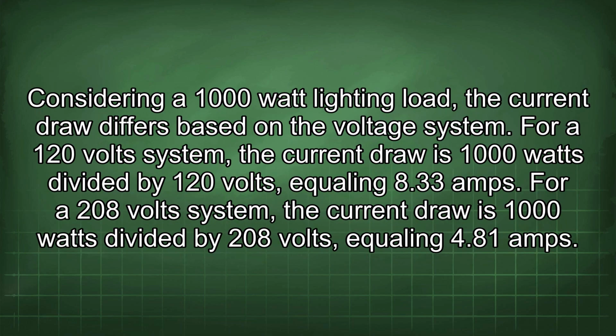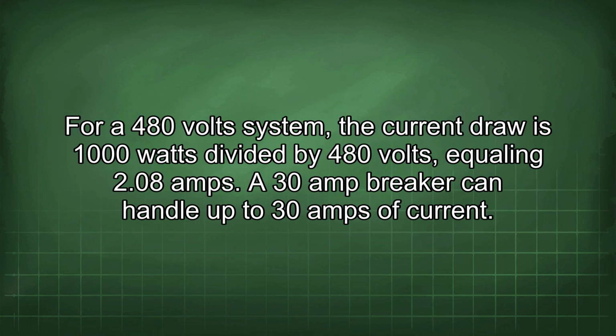Considering a 1000 watt lighting load, the current draw differs based on the voltage system. For a 120 volt system, the current draw is 1000 watts divided by 120 volts, equaling 8.33 amps. For a 208 volt system, it is 1000 watts divided by 208 volts, equaling 4.81 amps. For a 480 volt system, it is 1000 watts divided by 480 volts, equaling 2.08 amps.